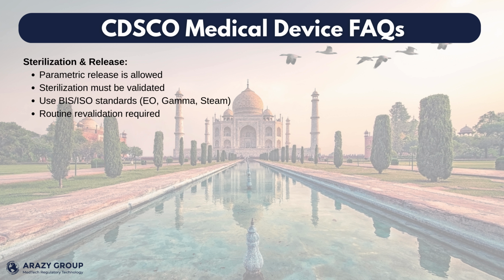Another frequent query concerns the release of sterilized devices based on parametric release without batch-wise testing. CDSCO has confirmed that this is permissible, provided the sterilization process is validated in accordance with applicable BIS or ISO standards, such as EO sterilization, ISO 11135, gamma sterilization, ISO 11137, and steam sterilization, ISO 17665. Parametric release is acceptable where validation and routine revalidation are maintained, ensuring flexibility while upholding stringent control over sterilization quality.